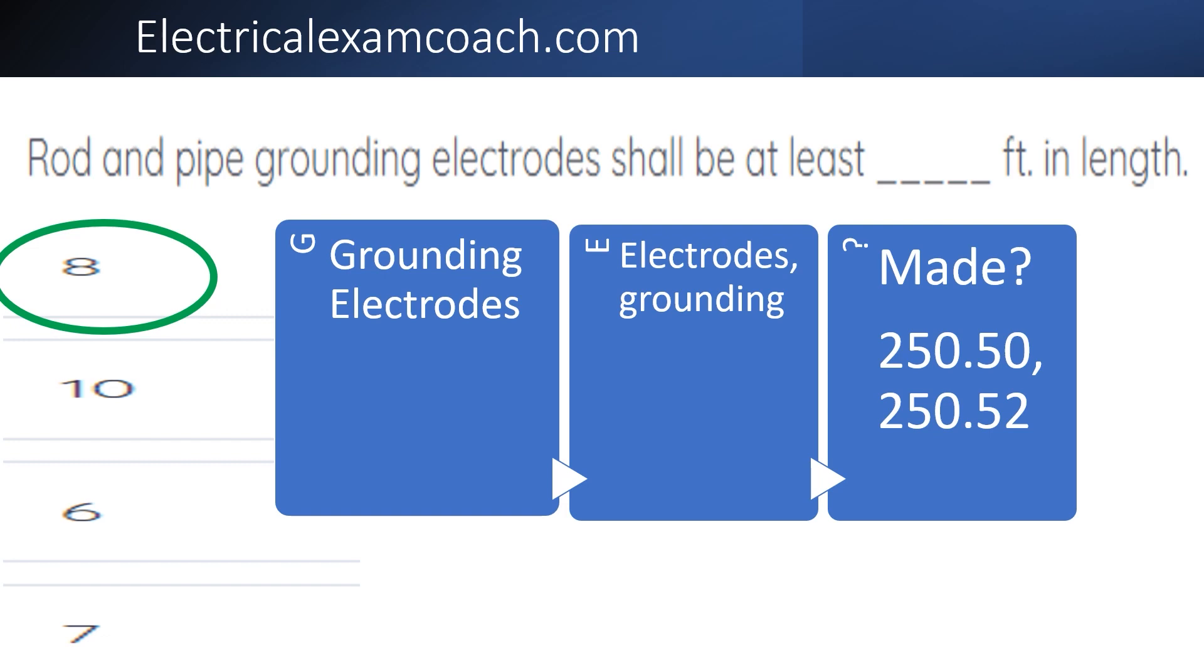So when we head to 250.50, we're going to start looking at our black bold headings. Great. I feel like we're in the right section. And when we get to 250.52, we find exactly what we're looking for using our black bolt heading method until we find something about rods or pipes. Sure enough, when we get there, we find it and we find that it's required to be eight feet.